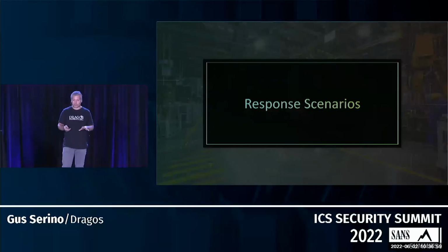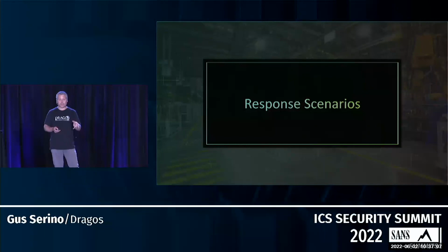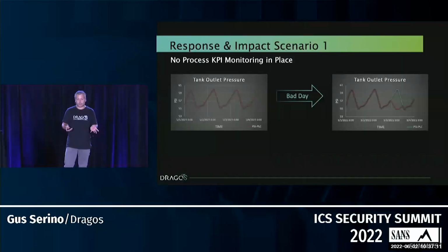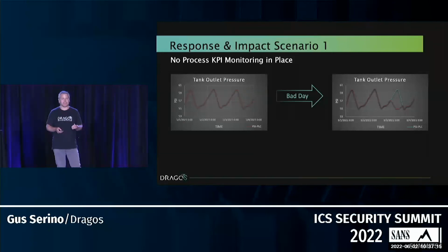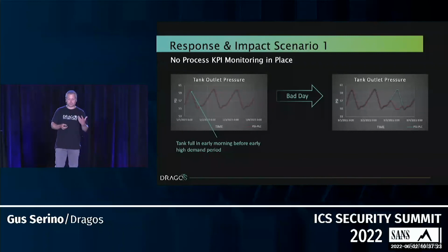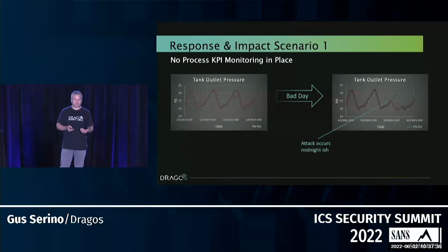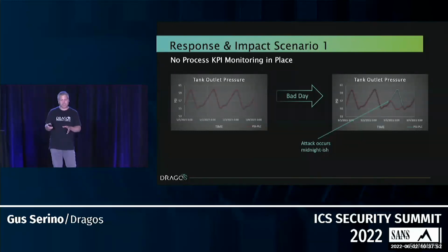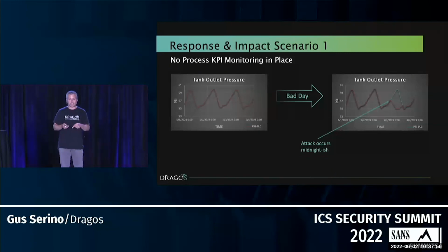So I just want to quickly go through a couple of response scenarios, without and then with that in place, to show how this may help. Here on the left-hand side we have a typical graph of tank level and outlet pressure throughout the day. Normally a water tank will be cycled throughout the day to keep the water fresh, so it gets filled before the morning high demand period, drains down throughout the day, and gets filled up again with those pumps. In my hypothetical scenario, the adversary knows when to do this. They stop the pumping, and the operator continues to see the green line going up, so everything looks fine on the HMI. At the same time, the actual tank level, the red line, continues to draw down due to demand.